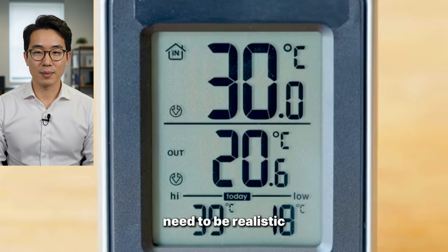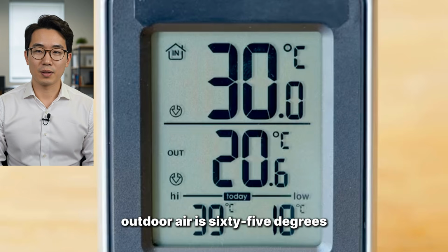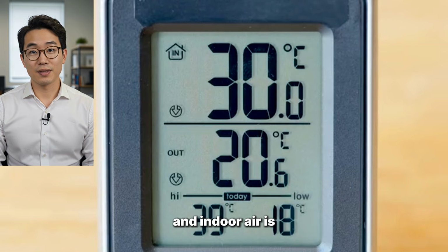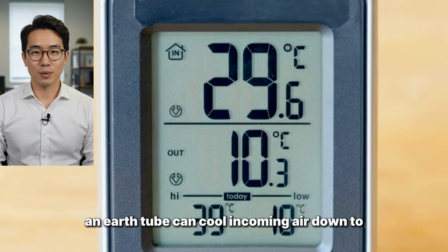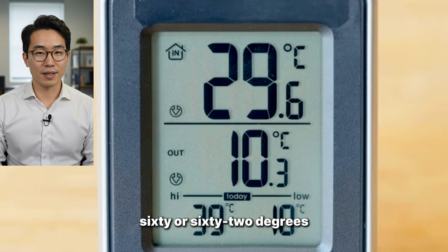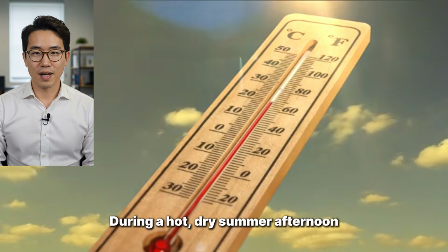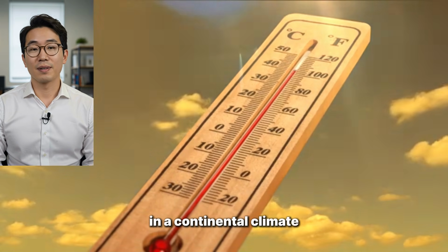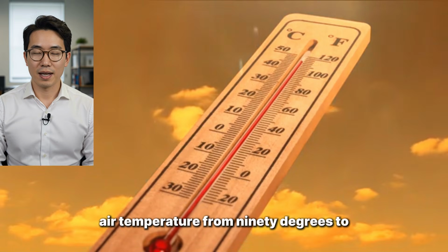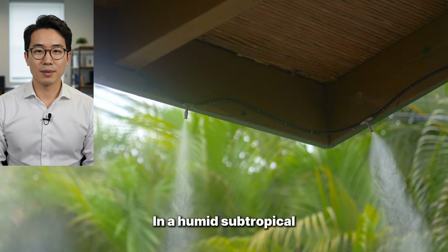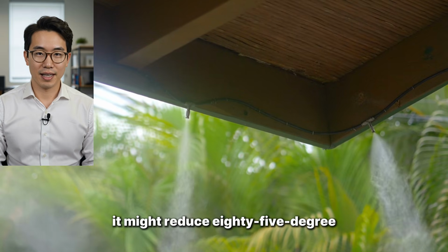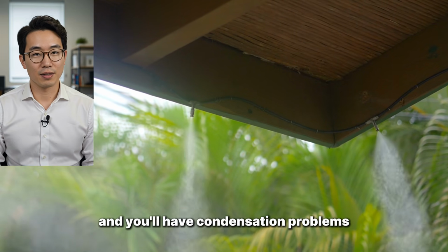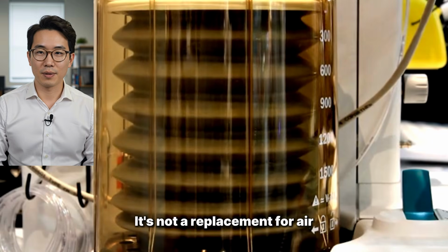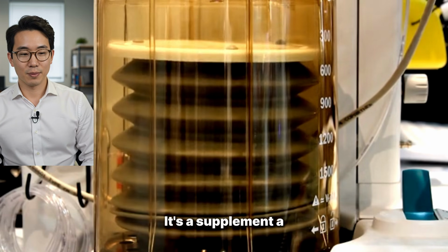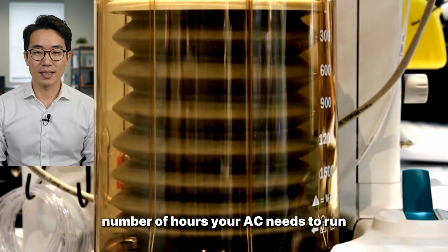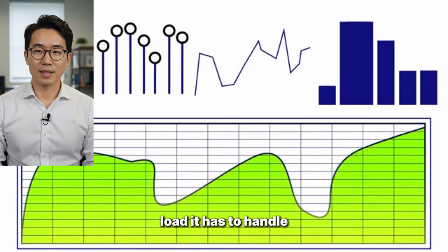Performance expectations need to be realistic. In a mild spring day when outdoor air is 65 degrees and indoor air is 75 degrees, an earth tube can cool incoming air down to 60 or 62 degrees. That's real thermal benefit. During a hot, dry summer afternoon in a continental climate, it might reduce outside air temperature from 90 degrees to 75 degrees. In a humid subtropical climate during summer, it might reduce 85-degree air to 78 degrees, and you'll have condensation problems. It's not a replacement for air conditioning in extreme heat. It's a supplement, a way to reduce the number of hours your AC needs to run, and reduce the total cooling load it has to handle.